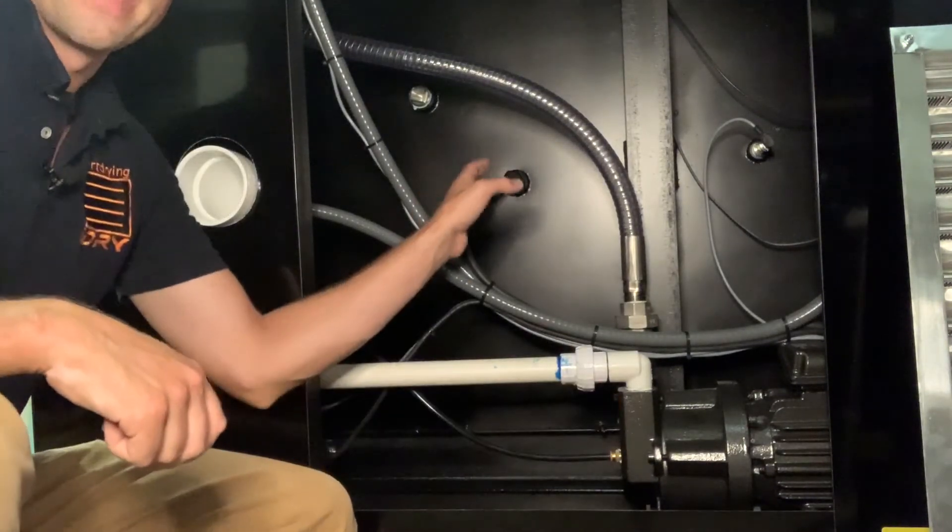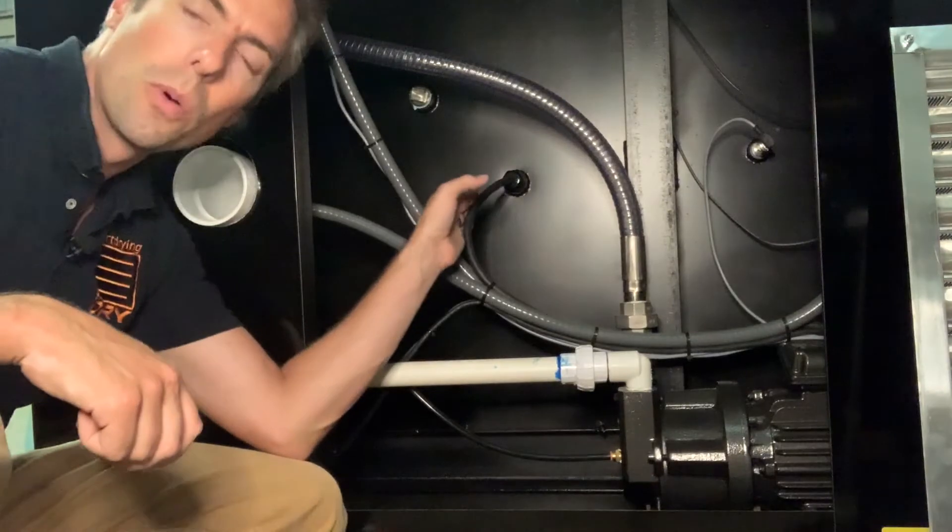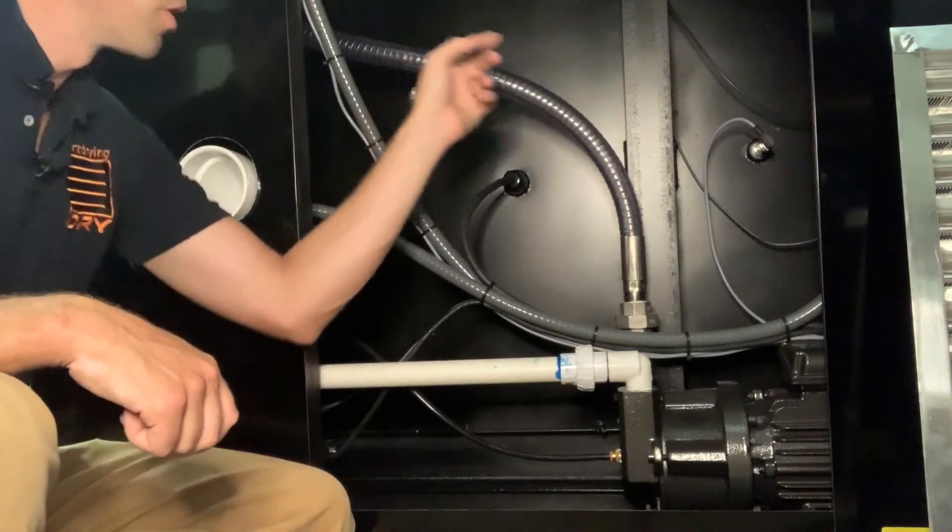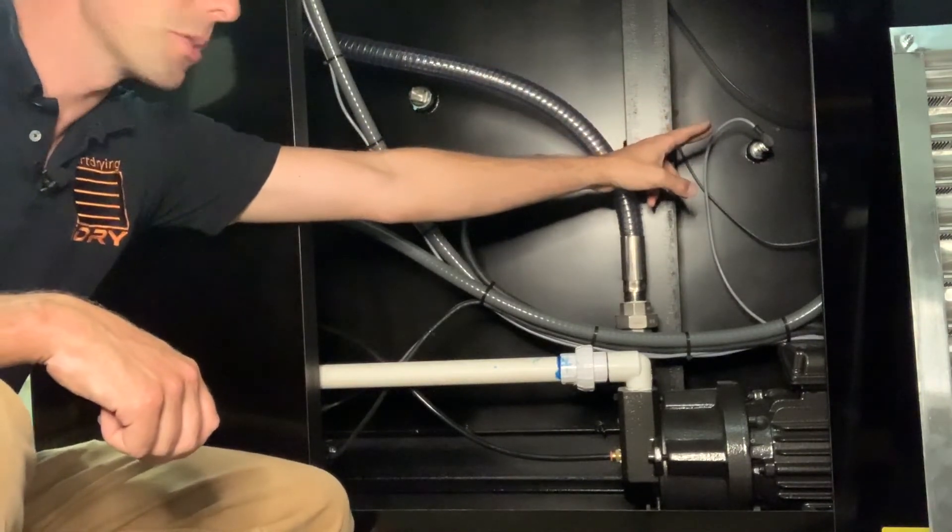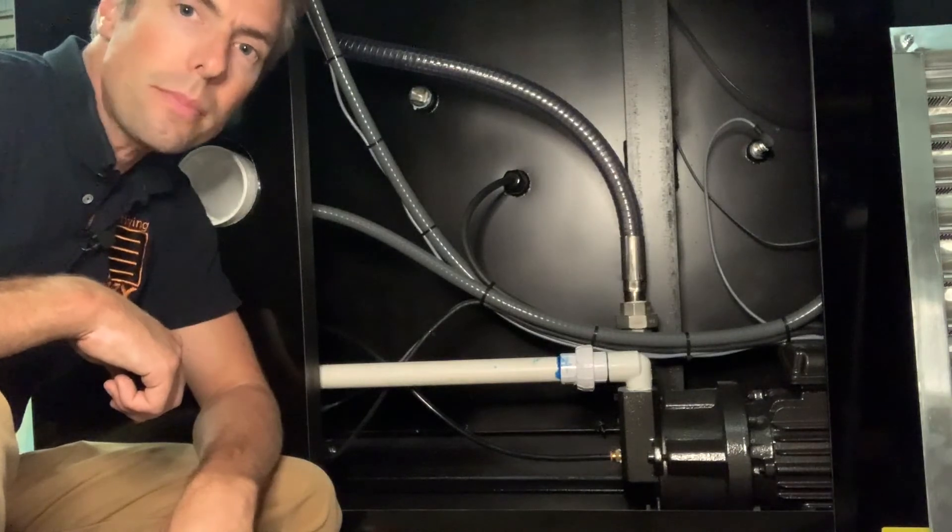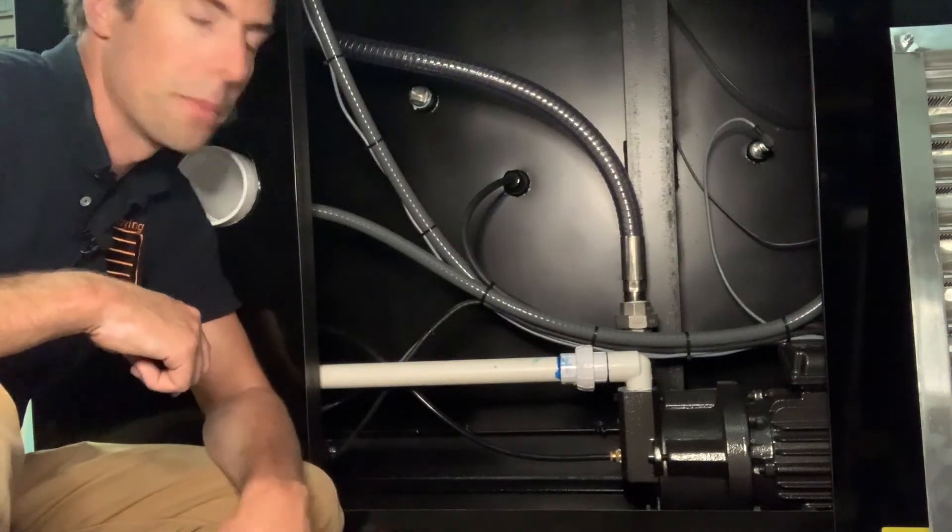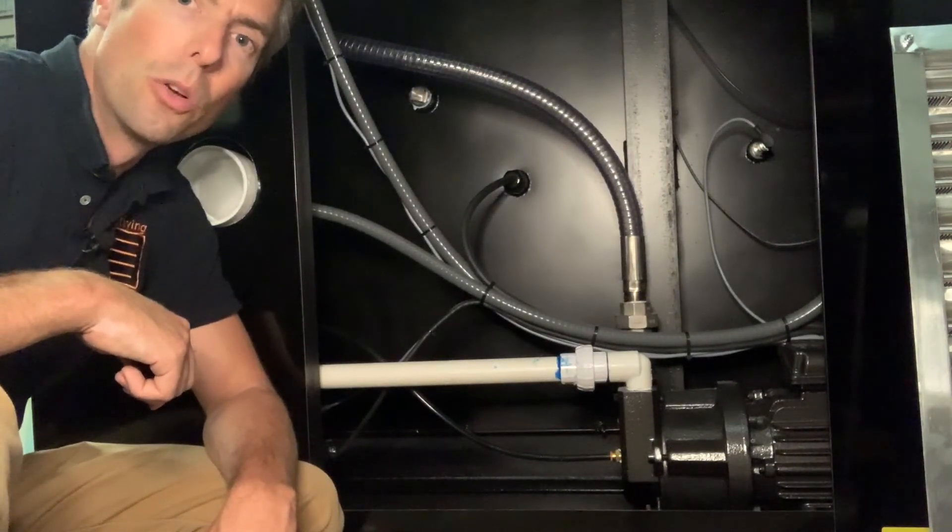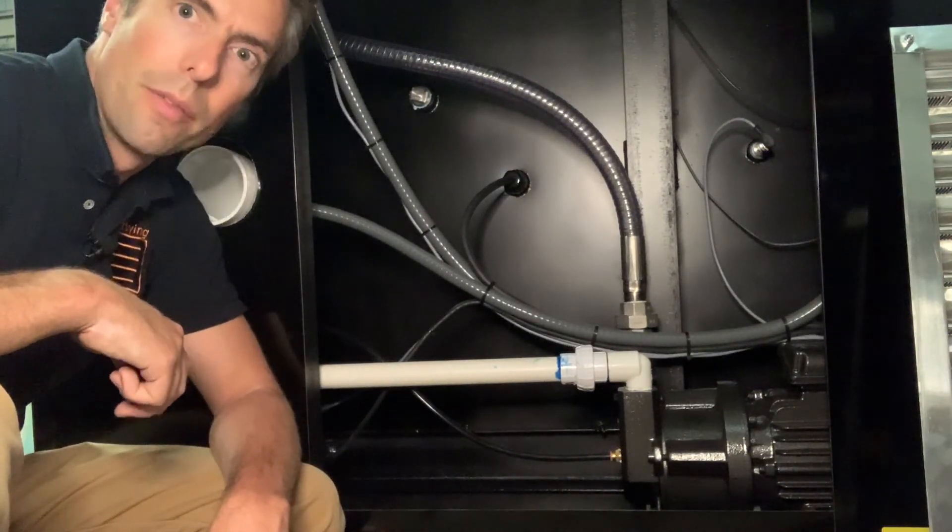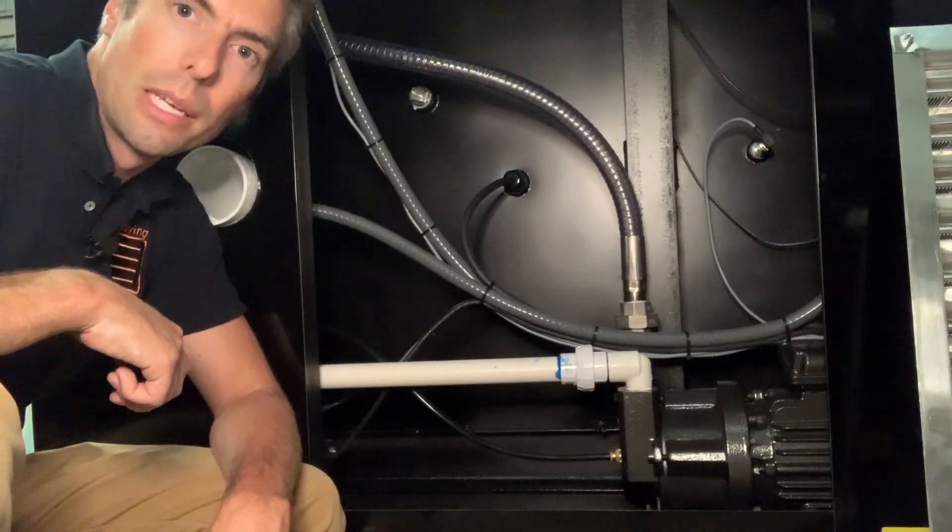We also have back here connections for the fan motor, which is inside the kiln. Different RTD sensors for temperature sensing. And we have the electric heating elements back here as well. All really easily accessible once you remove those louvers, but none of which requires much maintenance or work, but it is easily accessible.